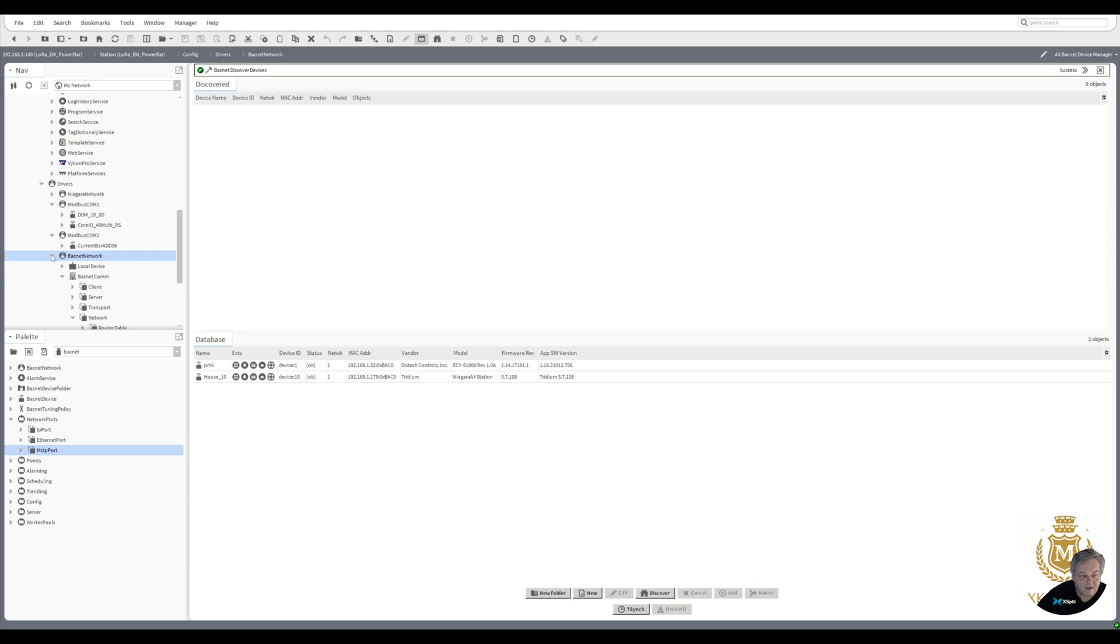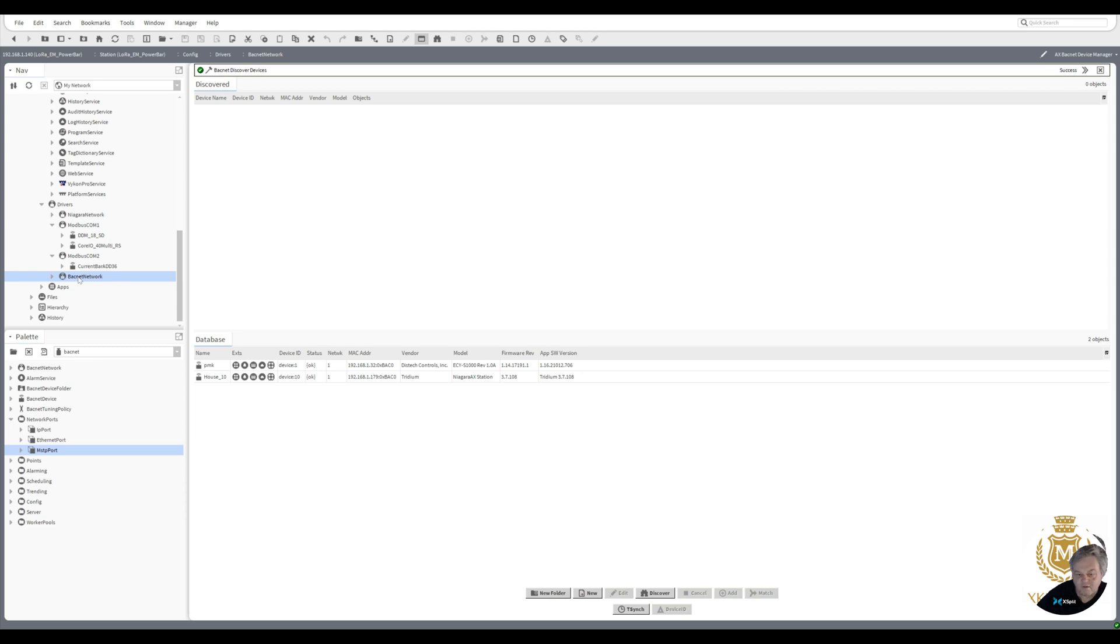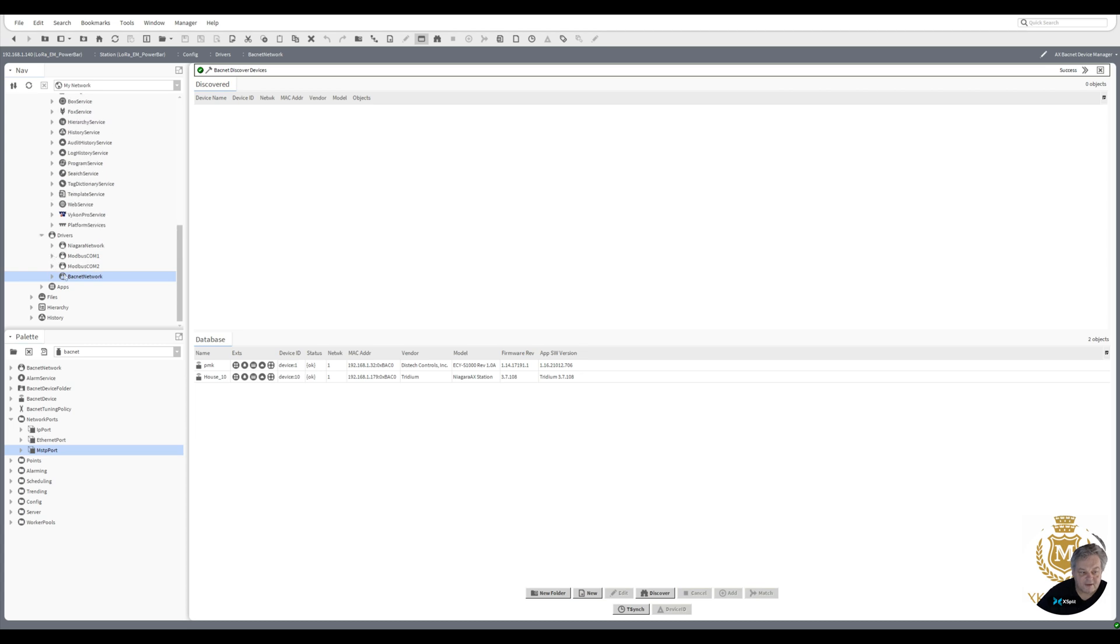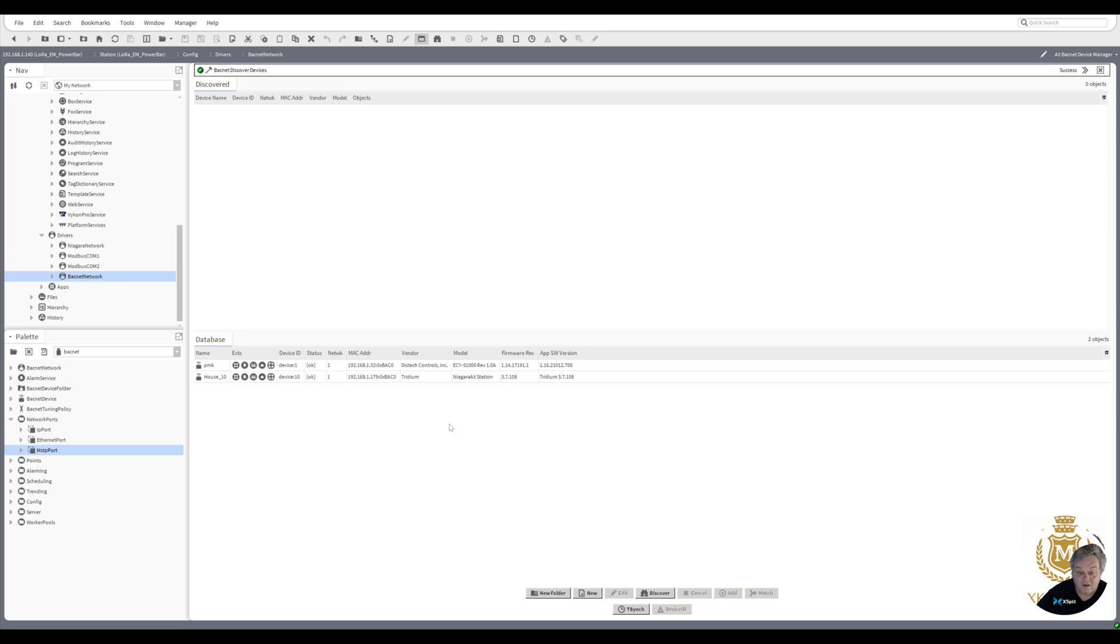That's it with your BACnet. That's how you install BACnet IP and MSTP. I prefer Modbus as I've said, but BACnet is very simple. I believe that BACnet uses more resources than Modbus, hence that's why I prefer Modbus. Any IO that I use, input-output modules, I would always use Modbus rather than BACnet. And LON, LON I would not use. If I had to put an order of preference, it would first be Modbus, then it'd be BACnet, and then at the end would be LON. I would not use LON. I've got to buy an extra module, and I can only use it on a JACE 8000. I can't use it on a Mac 36 with built-in IO. So LON is not a good option for me. Modbus is the best option for me. Thank you for watching.